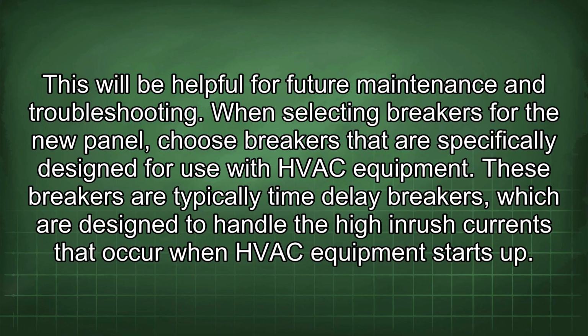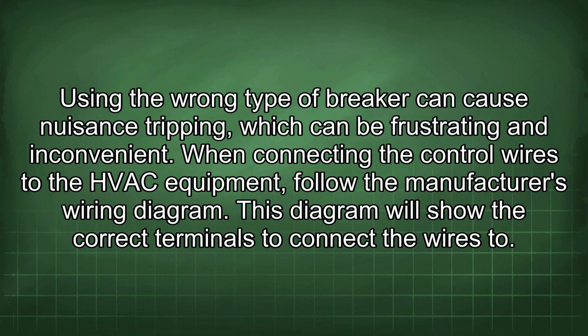When selecting breakers for the new panel, choose breakers that are specifically designed for use with HVAC equipment. These breakers are typically time delay breakers, which are designed to handle the high inrush currents that occur when HVAC equipment starts up. Using the wrong type of breaker can cause nuisance tripping, which can be frustrating and inconvenient.